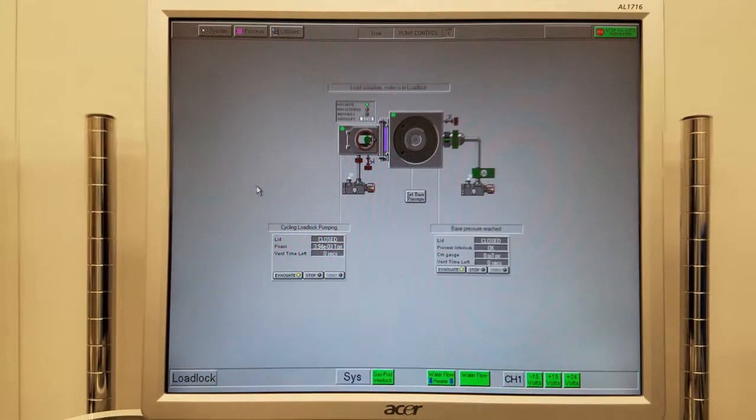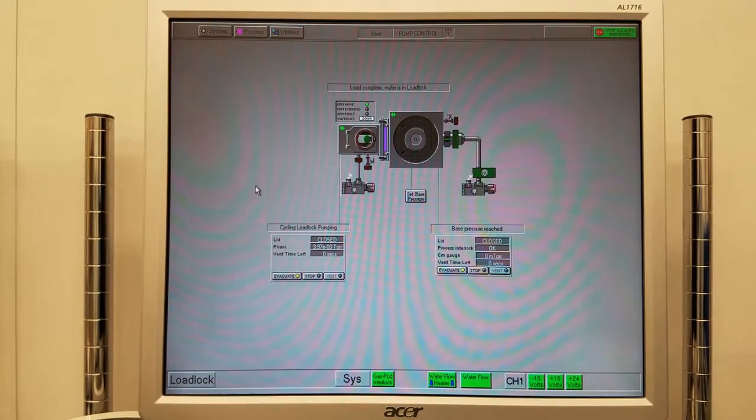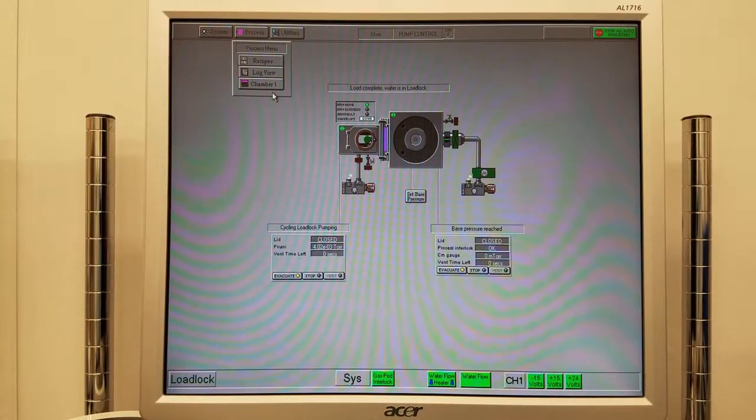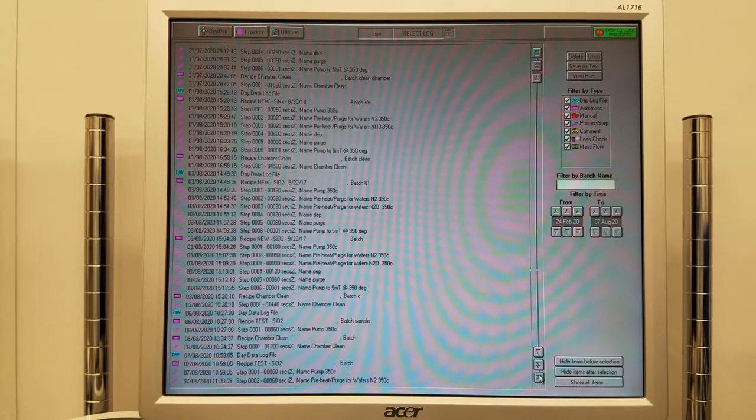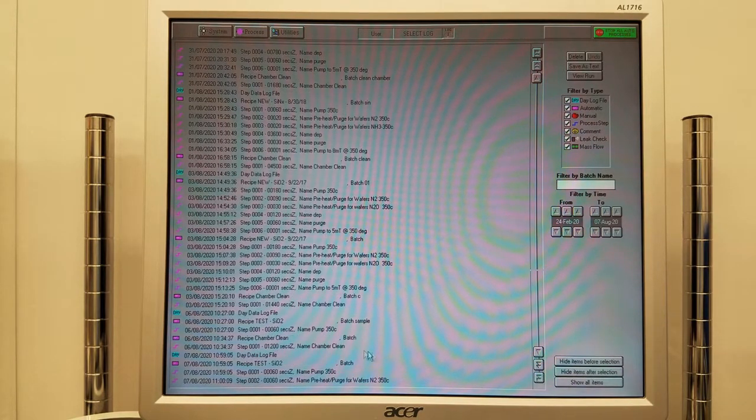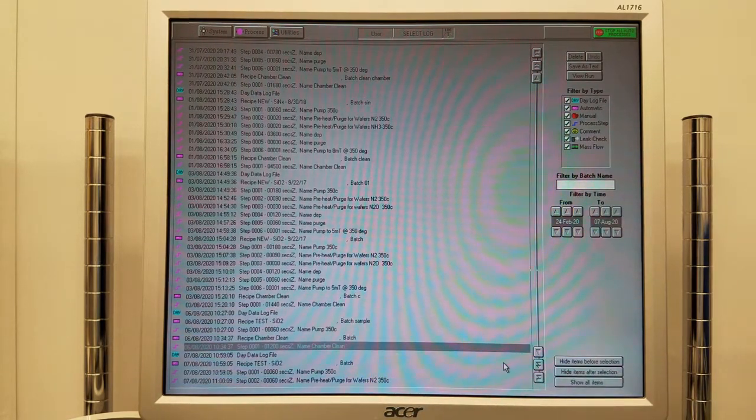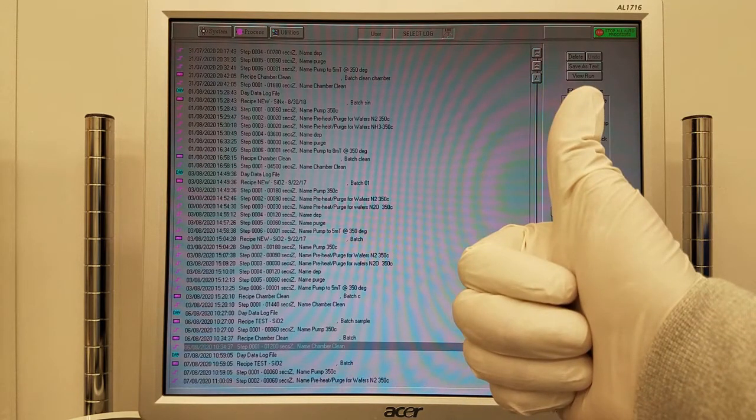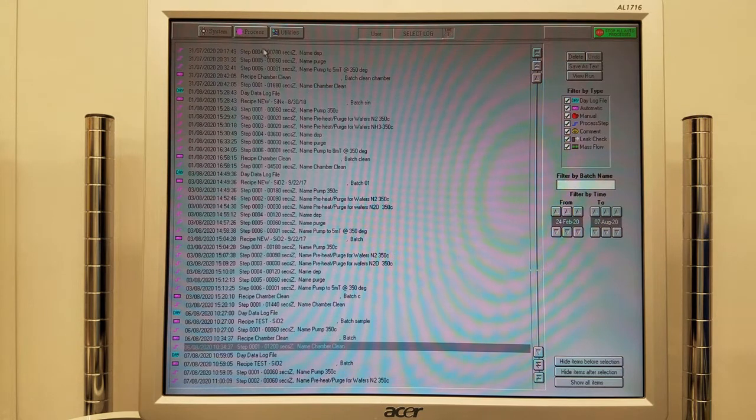First, we need to check the recipe log and make sure that the previous user ran a chamber clean. Click process, log view, scroll to the bottom, and check for the chamber clean. If the last process run was a chamber clean, you may proceed. Otherwise, please run a chamber clean for the previous user's deposition time plus 15 minutes before your process. Click System and Pumping to go back to the previous menu.